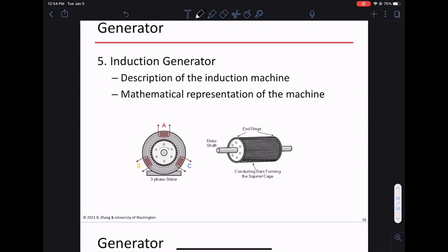Whereas a synchronous generator requires its own magnet, requires its own speed. A synchronous generator establishes its own speed. So it's sort of bulkier, more expensive, heavier to build. Okay, so these are the differences. But then if you look at the induction generator, when might you not want to use it for wind? It's very robust, right? Super robust. It's very cheap, it's fairly light, actually. There's not much going on in the machine. But maybe what are some of the drawbacks of induction generators?